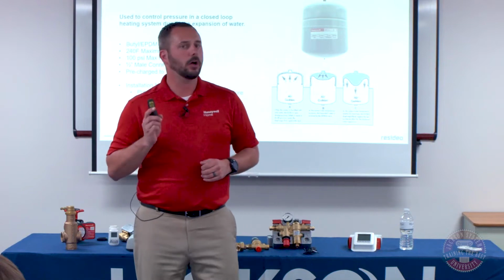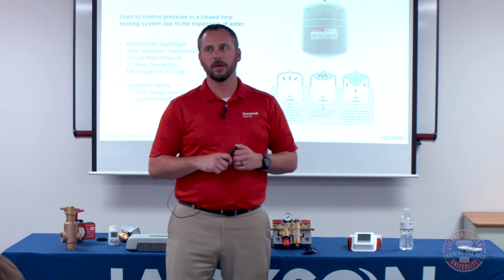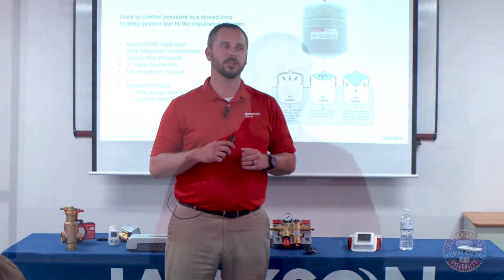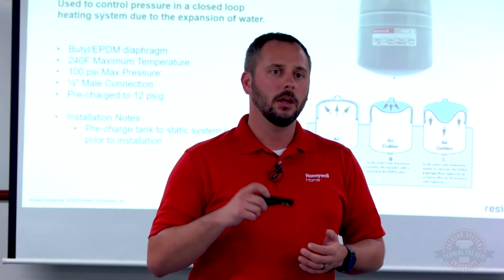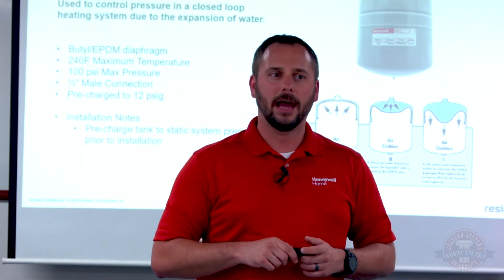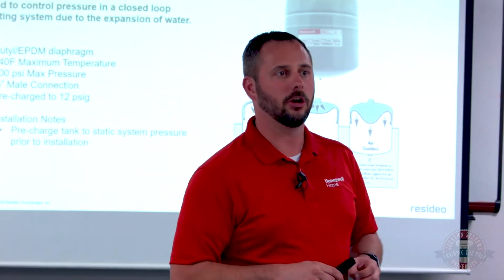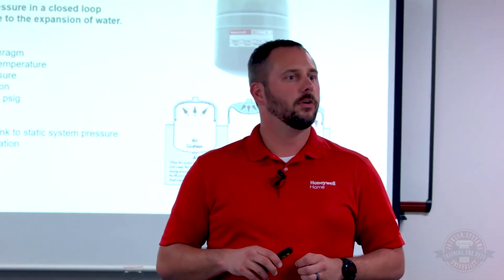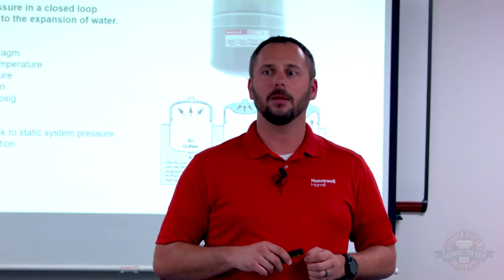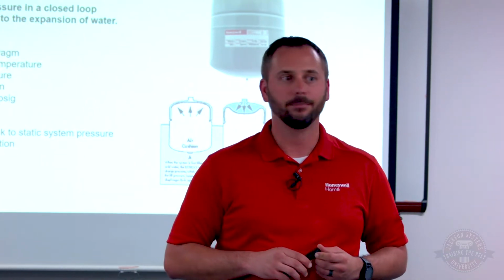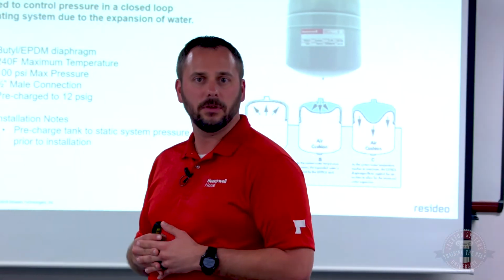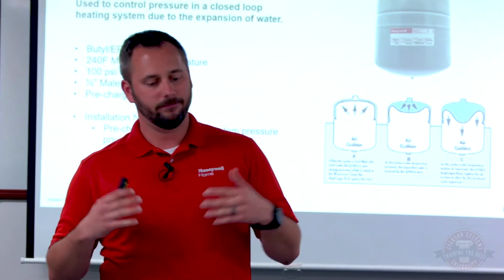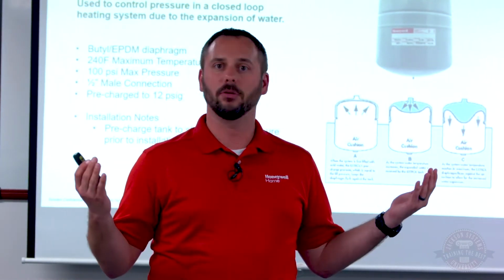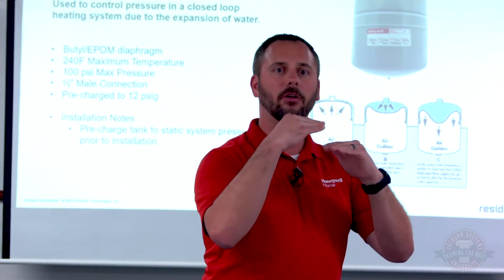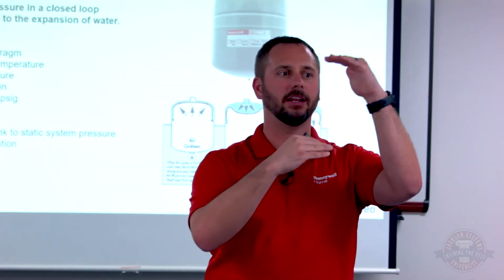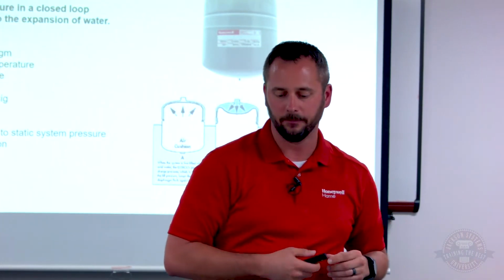The other thing that I will caution you on, I've been on job sites that get commissioned when it's -30 outside. Make sure you pressurize that in the conditioned temperature you're going to be operating in. Because if you try to pump that thing up at -30, it's not going to be the same pressure when it starts to warm up. So you match the expansion tank to 15 pounds, and then you also want to hook it in and basically run it at the same pressure, because you want to balance pressure between the water side and the air side to get full acceptance inside that expansion tank.